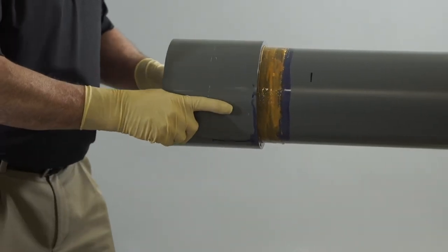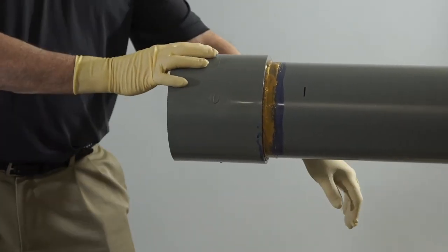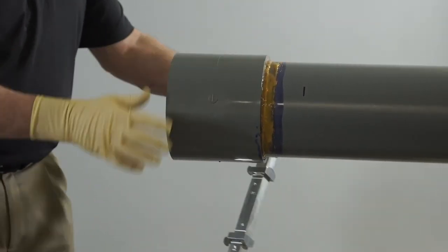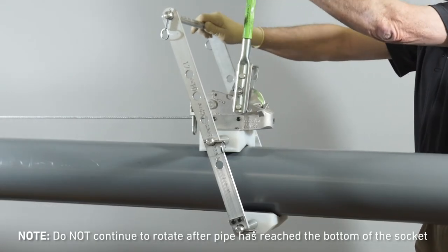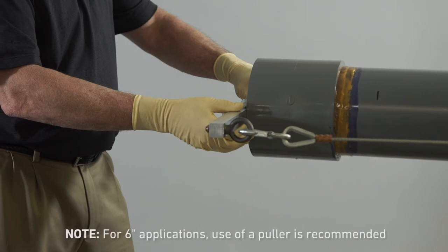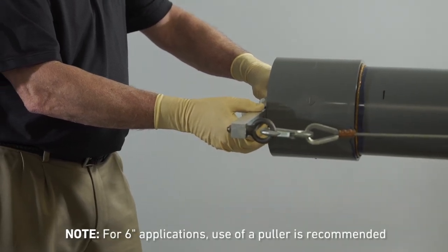Immediately while the solvent cement is still wet, insert the pipe into the fitting socket with one smooth insertion action. If utilizing a pipe puller, ratchet the pipe puller until reaching the bottom of the socket. Hold the pipe and fitting together for a minimum of 30 seconds to avoid the pipe from pushing out.